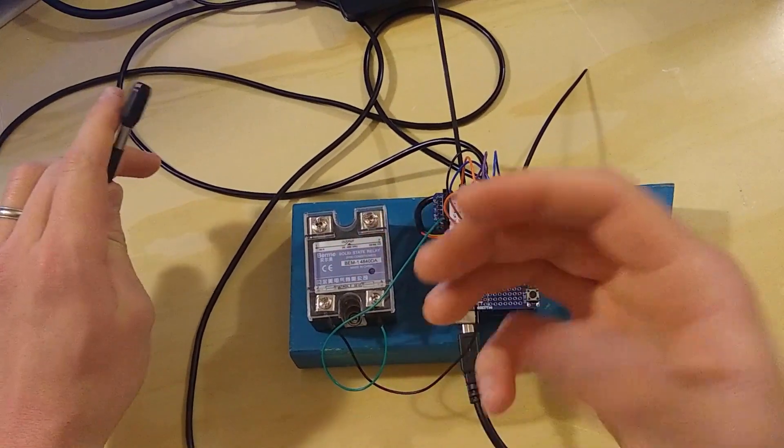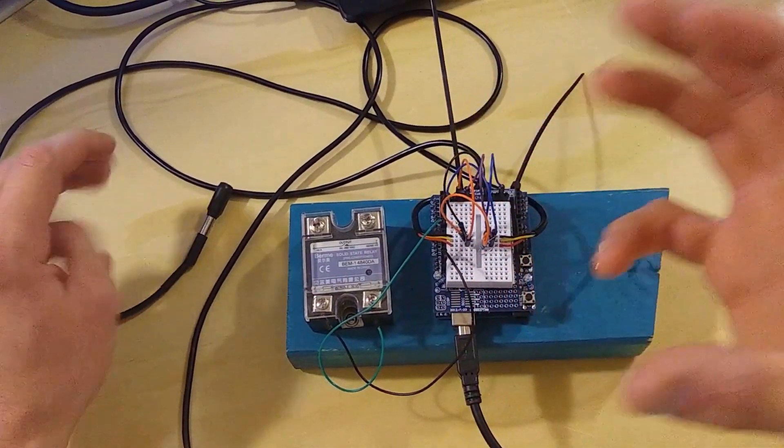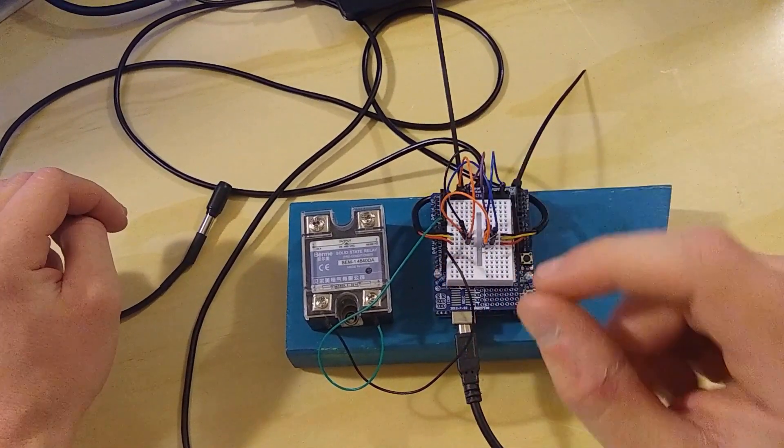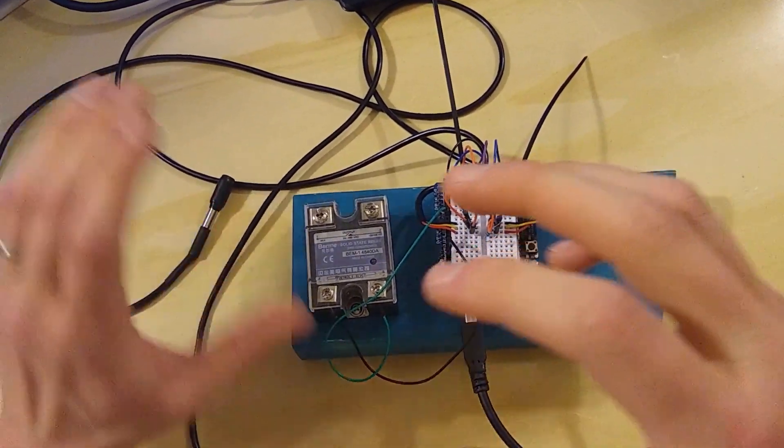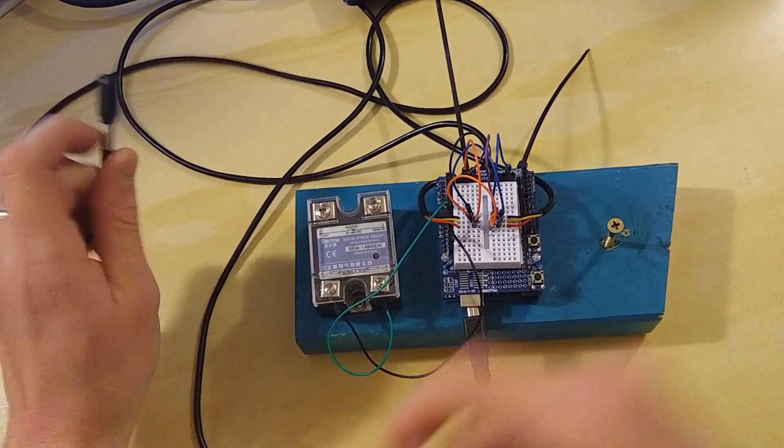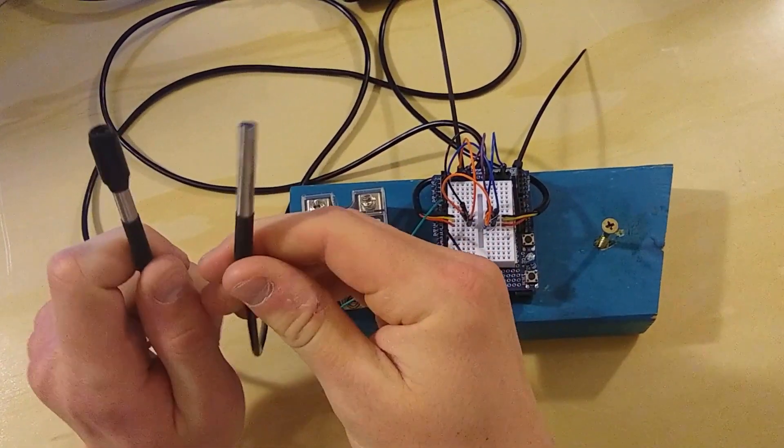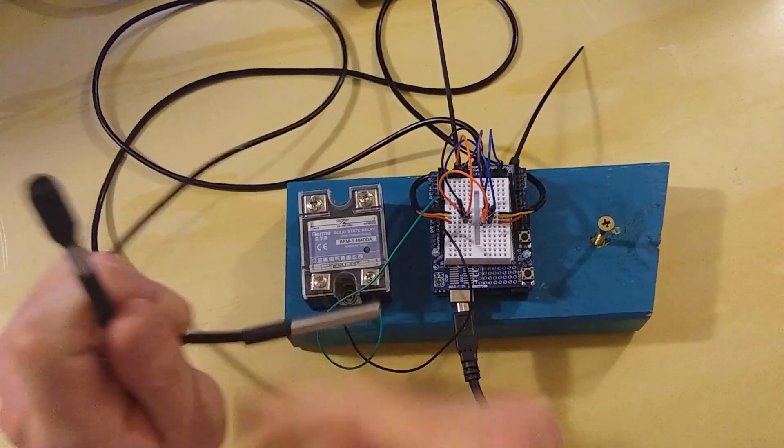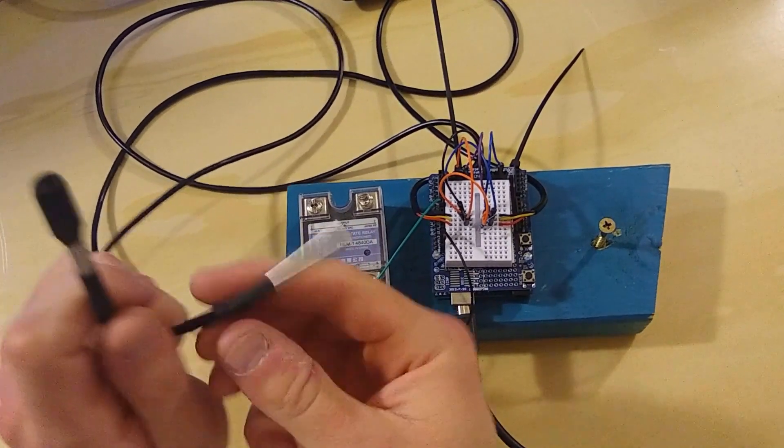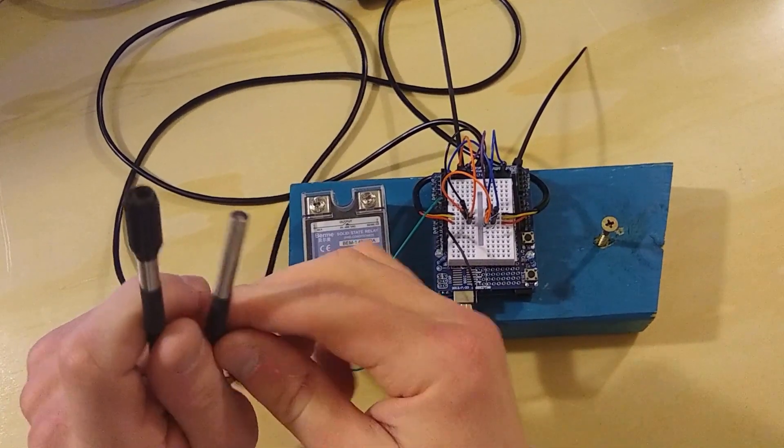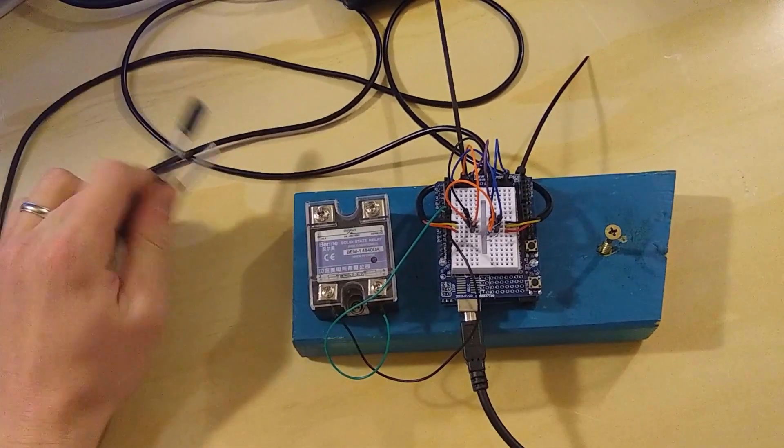When it's frozen, it basically just shuts off the relay, which shuts off the compressor, which allows that radiator to thaw, allowing us to not have the ice build up. And so that's why there are two temperature probes, and that's why on your commercial units, they have two temperature probes as well.